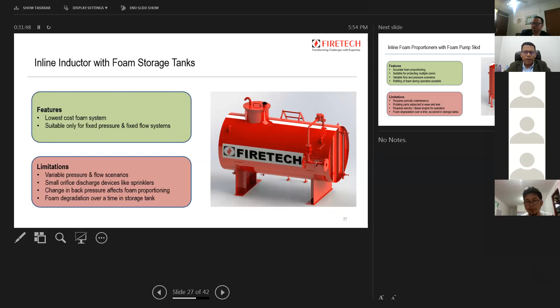Next, James. Now these are inline foam proportioners with foam pump skids. Here you can see there is an atmospheric foam storage tank and there is a skid which consists of a foam pump. The features are that it does accurate foam proportioning. You can use it for protecting multiple zones. So 5, 6, even 10 or 15 zones can be protected by this type of system. It can cater to variable flow and variable pressure scenarios. And refilling of the foam is possible during operation.